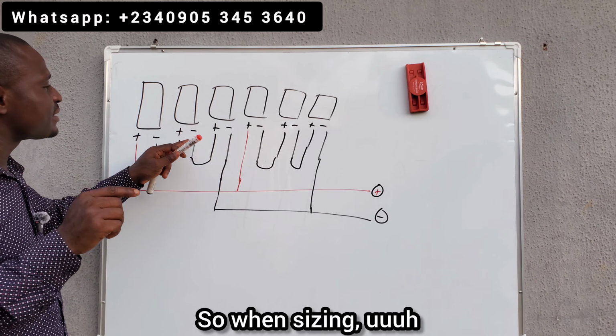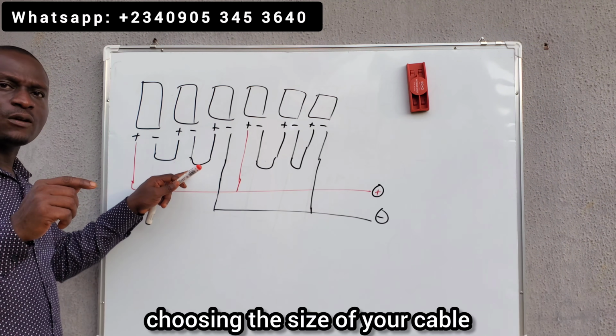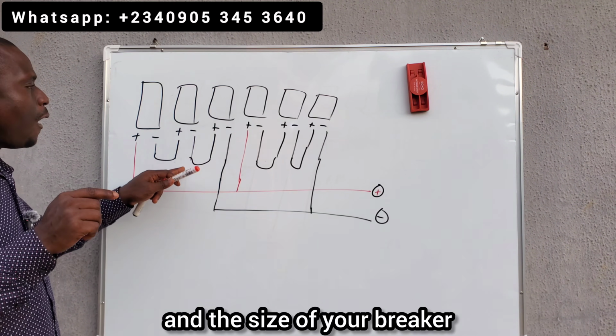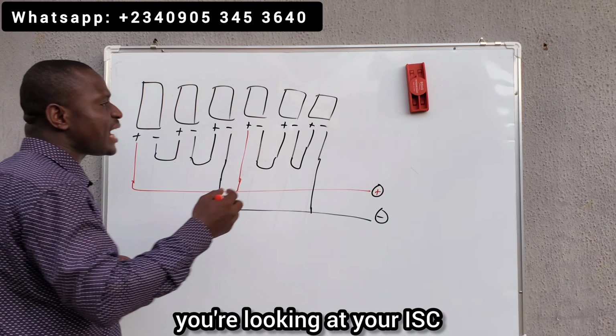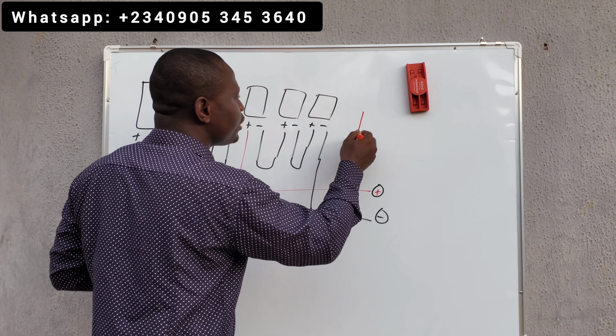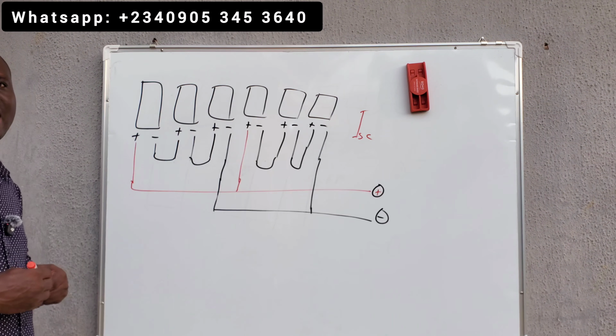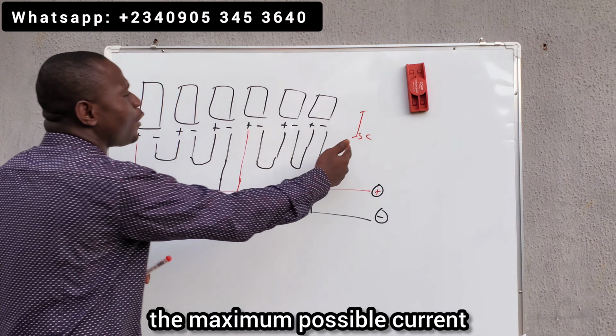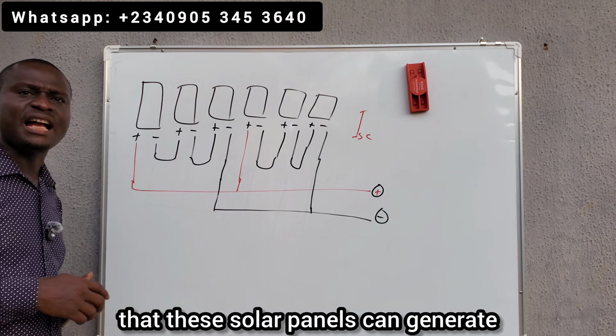So when sizing and choosing the size of your cable and your breaker, you're looking at your ISC, your short circuit current, the maximum possible current that these solar panels can generate.